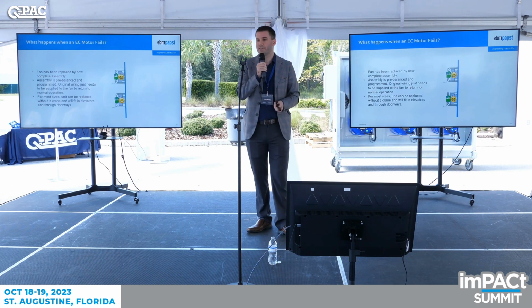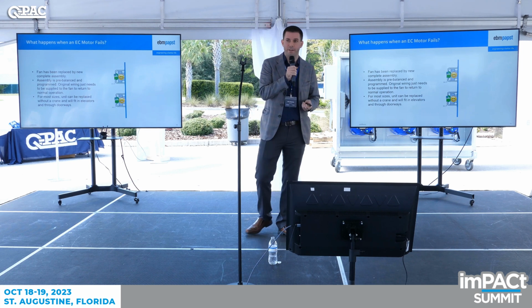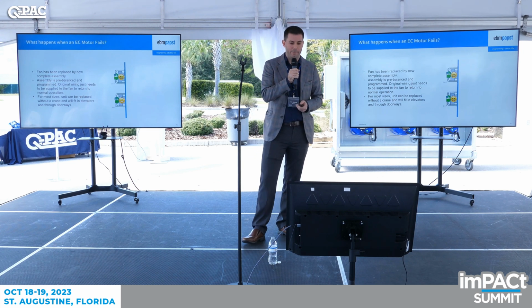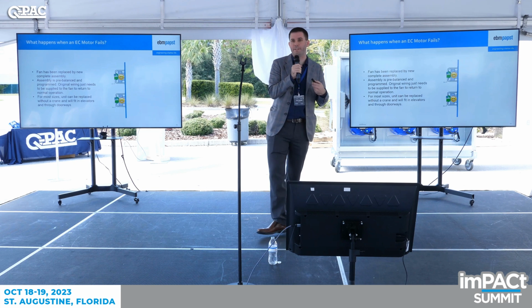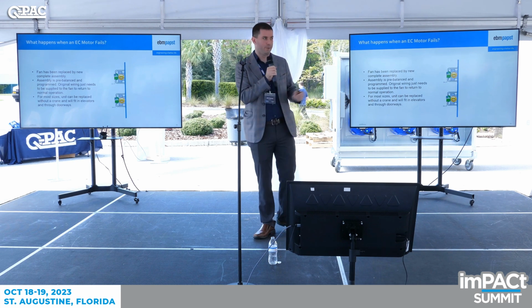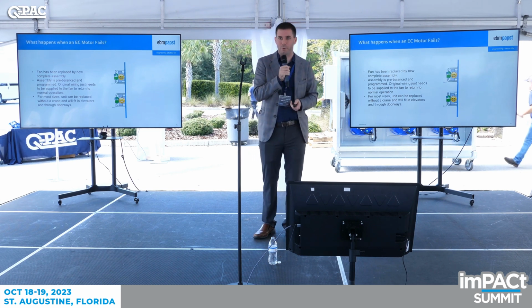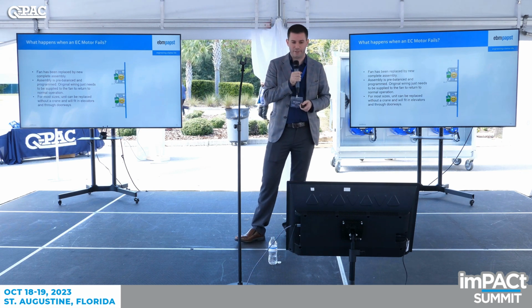Then the EC fan is replaced. The assembly is already pre-balanced, so you don't have to worry about it. It's already programmed. You don't have to do any programming. And for most sizes, the unit can be replaced without a crane. Fits in an elevator. One or two guys can lift it up, as we saw before. These are much, much smaller products.